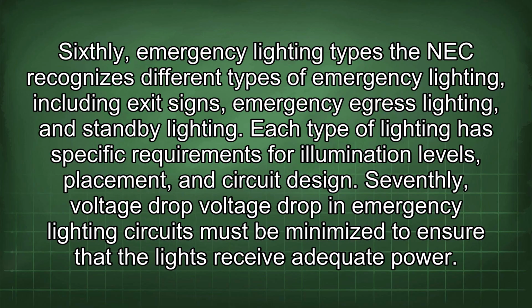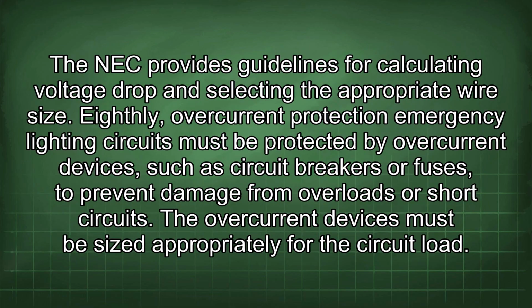Seventhly, voltage drop. Voltage drop in emergency lighting circuits must be minimized to ensure that the lights receive adequate power. The NEC provides guidelines for calculating voltage drop and selecting the appropriate wire size. Eighthly, overcurrent protection. Emergency lighting circuits must be protected by overcurrent devices, such as circuit breakers or fuses, to prevent damage from overloads or short circuits. The overcurrent devices must be sized appropriately for the circuit load.